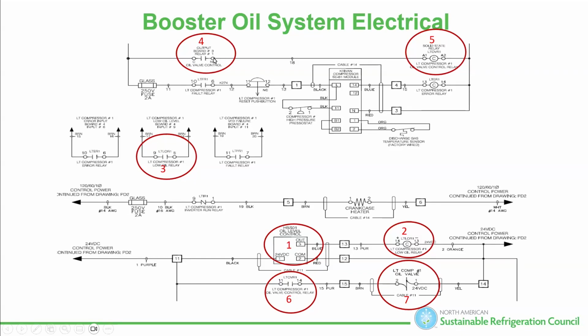I have two questions. Is the controller calling for it? Remember, is the controller calling for it? That's something we get all caught up with, and we're going to cover that in a minute. Listen to what the controller tells me. Is it calling? Yes or no? Is it calling? If it is, that should be closed.